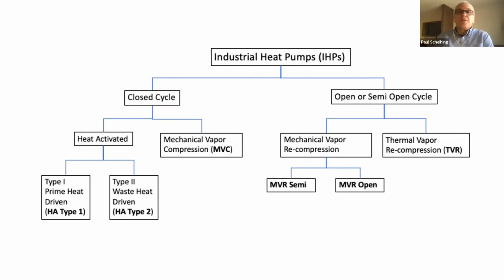First of all, you can design an industrial heat pump to be either closed, open, or semi-open cycle. Closed cycle, which we're more familiar with, which is what a residential heat pump would look like, has a heat exchanger on both the heat source and the heat sink to separate the heat pump working fluid from your heat source and sink. An open cycle is interesting in that you don't use a heat exchanger at all. You use the process fluid itself, such as steam, which would be compressed directly. And a semi-open is kind of in between the two, where you would have one heat exchanger applied on either the heat source or the sink stream.